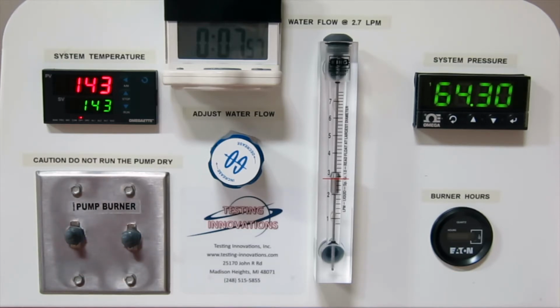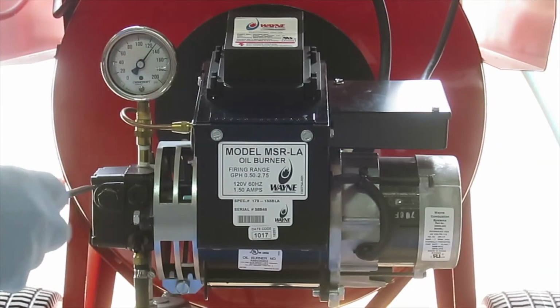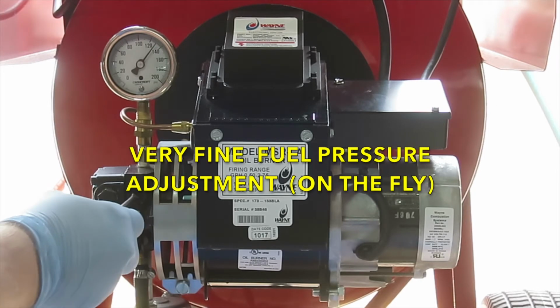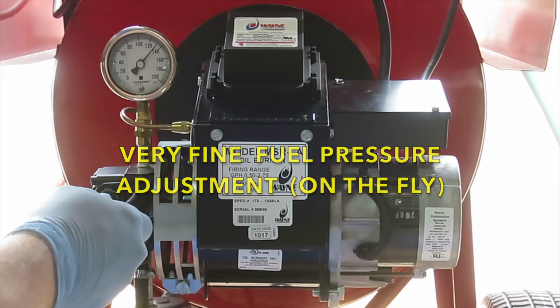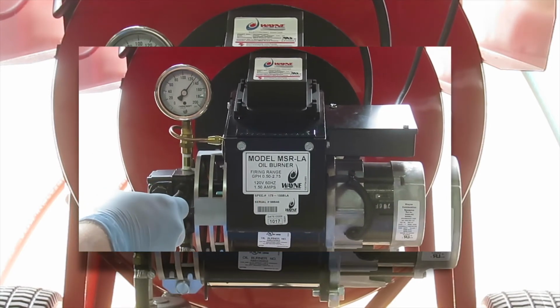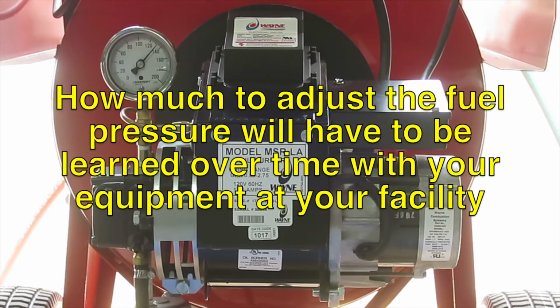The drop in temperature of the water will likely cause the system pressure to drop. During this time, the water flow rate increases. The correction for this would be to reduce the water flow rate to 2.7 liters per minute. This adjustment, however, will cause the pressure and temperature to drop further. The best answer at this point is to raise the fuel pressure a minuscule amount, but just how much to adjust the fuel pressure will have to be learned over time with your equipment at your facility.